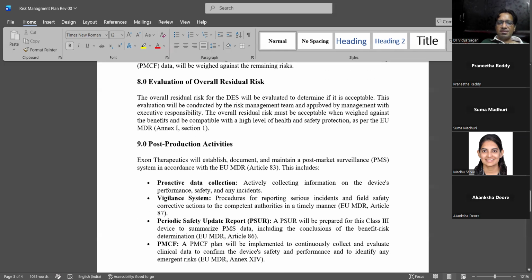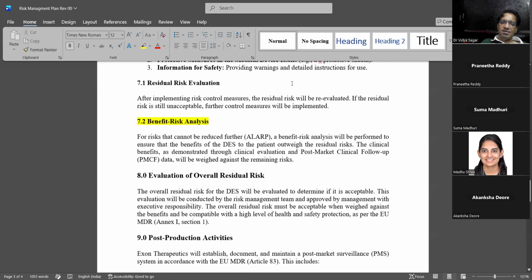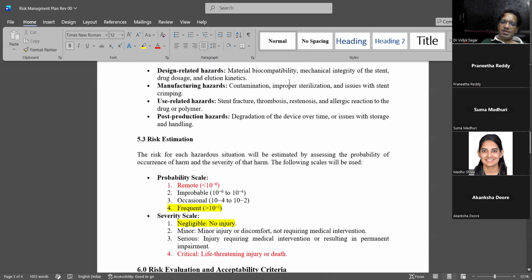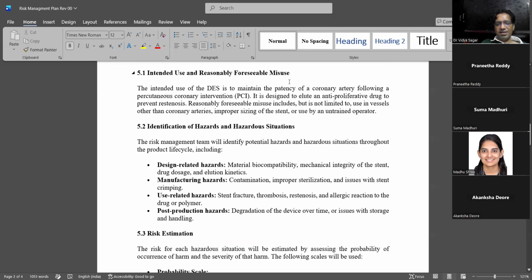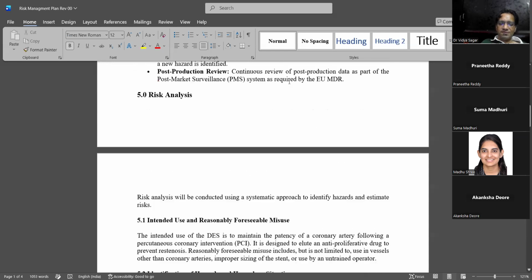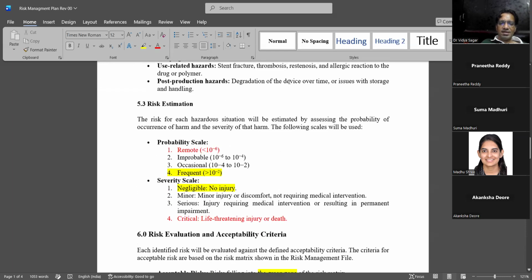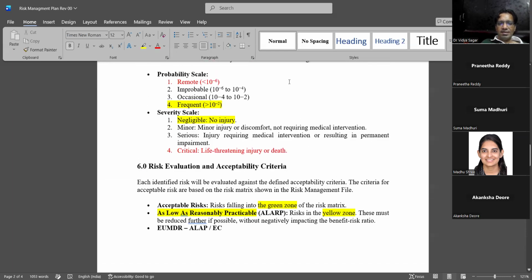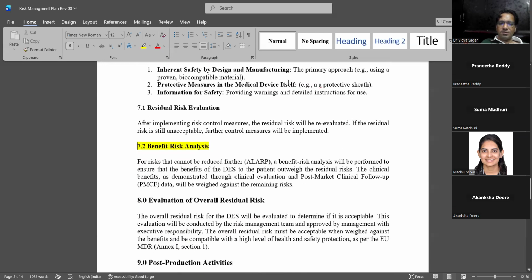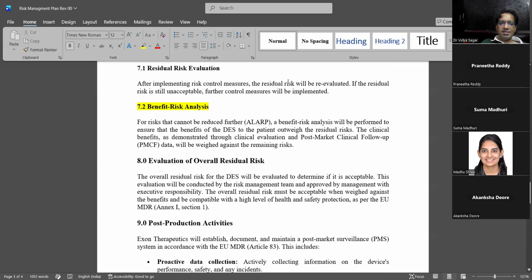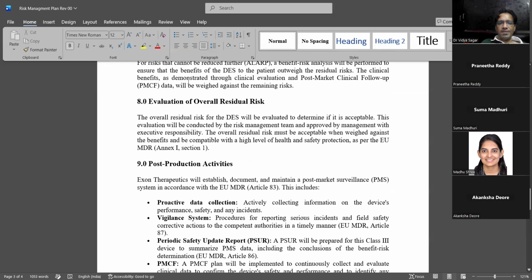Evaluation of overall residual risk. This is exactly what is there. The contents you see in 14971, you see in the plan. It's not that somebody in the middle of the night got an idea how to write a risk management plan, got a dream and wrote it. You just follow the standard. What are the contents in that?